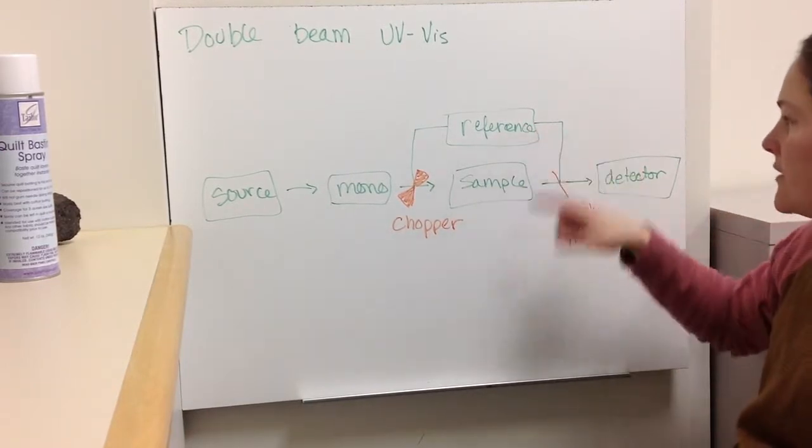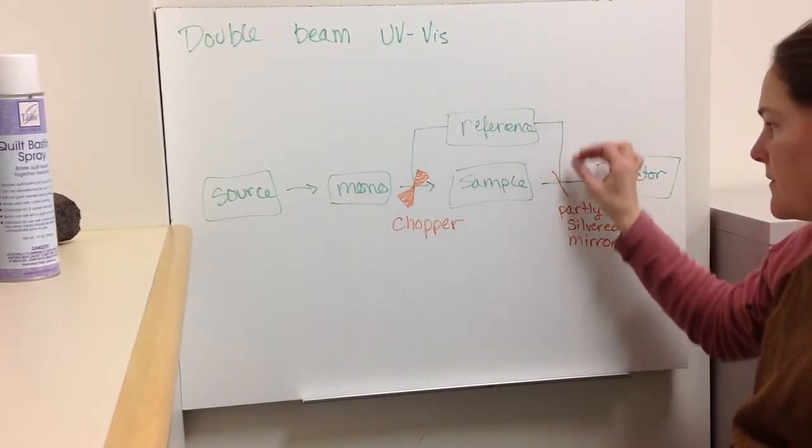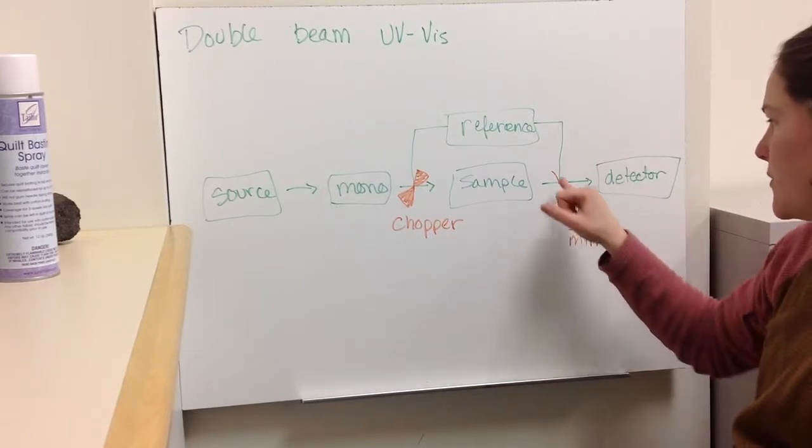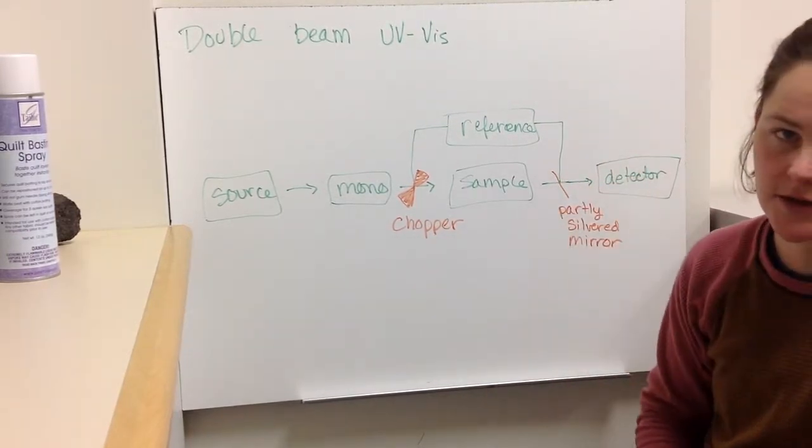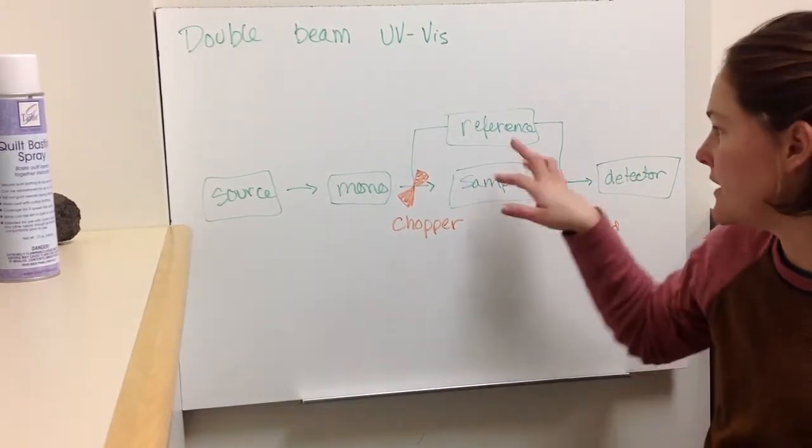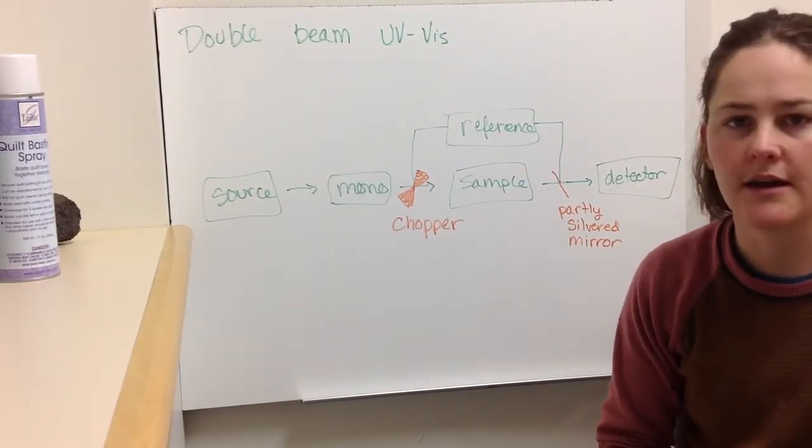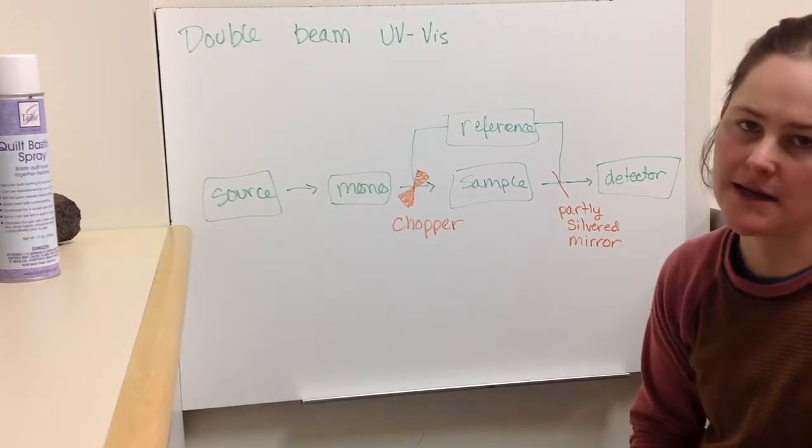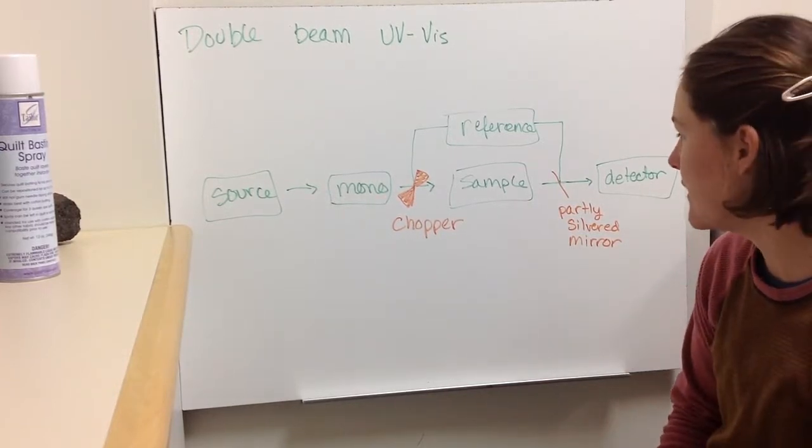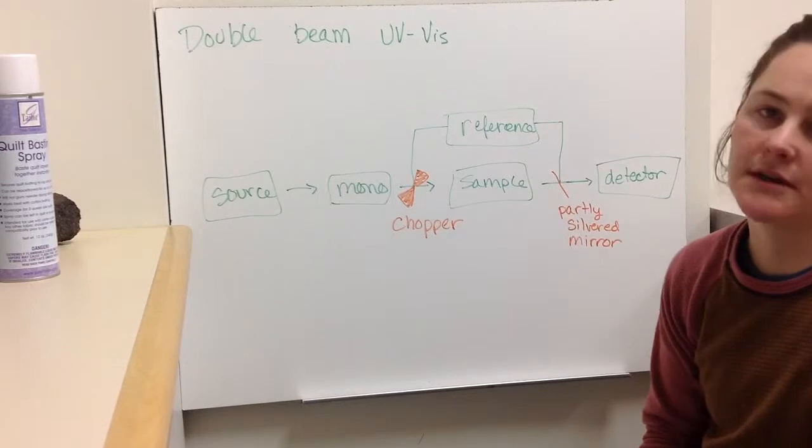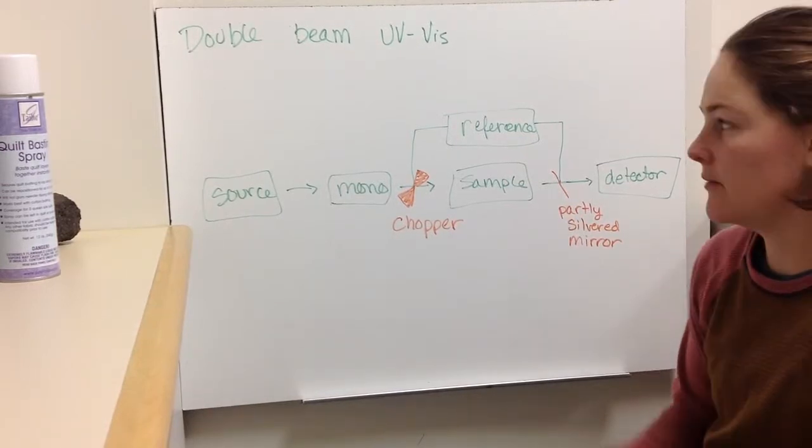So then you have light either through the reference or through the sample, then they come back together through a partially silvered mirror, and then they go to the detector. And so these cuvettes, whatever your sample's in, need to be closely matched. Same path length and everything, and then same media, dilution media. So that way, you really can isolate what signal is actually coming from the sample.